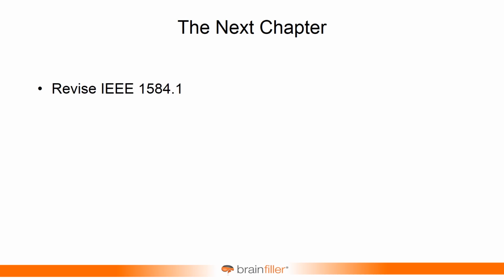So what's next? We're not done. There's going to be more work. Just because the latest edition of 1584 is about finished, and I said there's a few other hurdles that we have to clear yet, but it's almost finished, doesn't mean we're done. There's a lot more that we want to look at. And this is in no particular order, and there's no guarantees that this is exactly how we're going to handle this. But some things that we're kicking around, this first one actually is a guarantee. That's what we're going to take up at the next meeting. It's a revision of what's called IEEE 1584.1. And IEEE 1584.1 is basically what goes into an arc flash study, the scope and deliverables of an arc flash study. So since 1584 has been completely overhauled, we have to bring 1584.1 in sync with 1584. So this will be one of the first things that we begin to undertake.